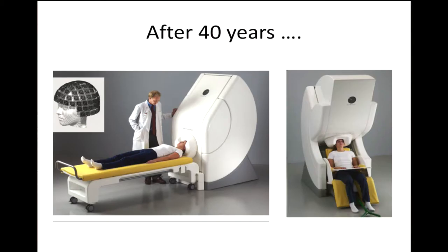You don't see any instrumentation, but it costs a whopping, I think, $3 to $4 million. So it's a very, very expensive device. And not only that, it needs at least $100,000 to $200,000 to maintain every year, because you have to replenish the liquid helium. All the superconducting SQUIDs are inside what we call a dewar, kept immersed inside the liquid helium chamber, and that liquid helium you have to replenish every year. So it's a very expensive piece of kit.